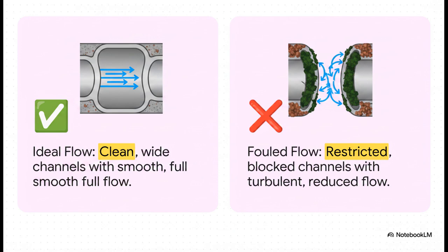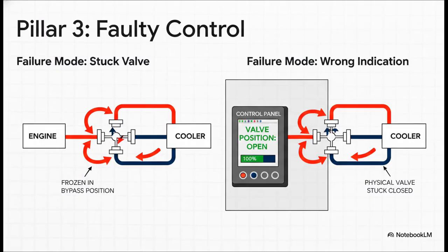But on the right, it's fouled. The passages are choked. Flow becomes turbulent and it's drastically reduced. Your surface area for heat exchange is gone. Your pressures might even look okay, but the thermal performance has disappeared. Pillar 3 is about faulty control.